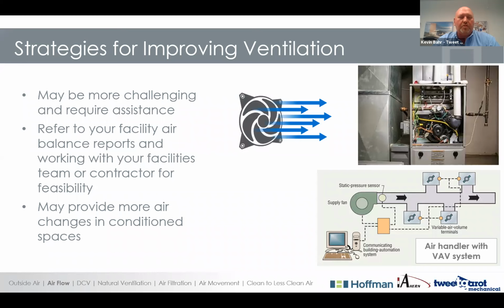I also show a picture of a typical air handler VAV system. Those systems are originally designed for your minimum airflow requirements for fresh air, minimum heating, minimum cooling, maximum heating, maximum cooling parameters. If you override those particular items through your building automation or manually, please record where they were to start with so you do not deviate away from your building design. A couple things that may occur is if you increase the amount of airflow in your traditional spaces by doing these recommendations, you may cause some discomfort with too much air blowing on people, create some nuisance calls. You may need an air balancer to assist you with this one if you choose this route, so they can reference the original status versus the manipulated status of your system. Next slide, please.